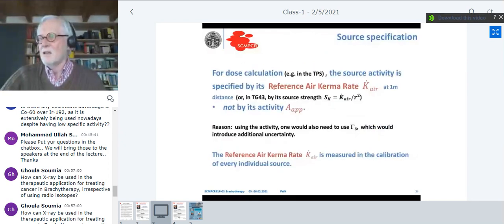Maybe we can probably stop with this slide here. For dose calculation, for instance in the treatment planning system, the source activity is specified by the reference air kerma rate at 1 meter distance, or in TG43, which we will speak about tomorrow.